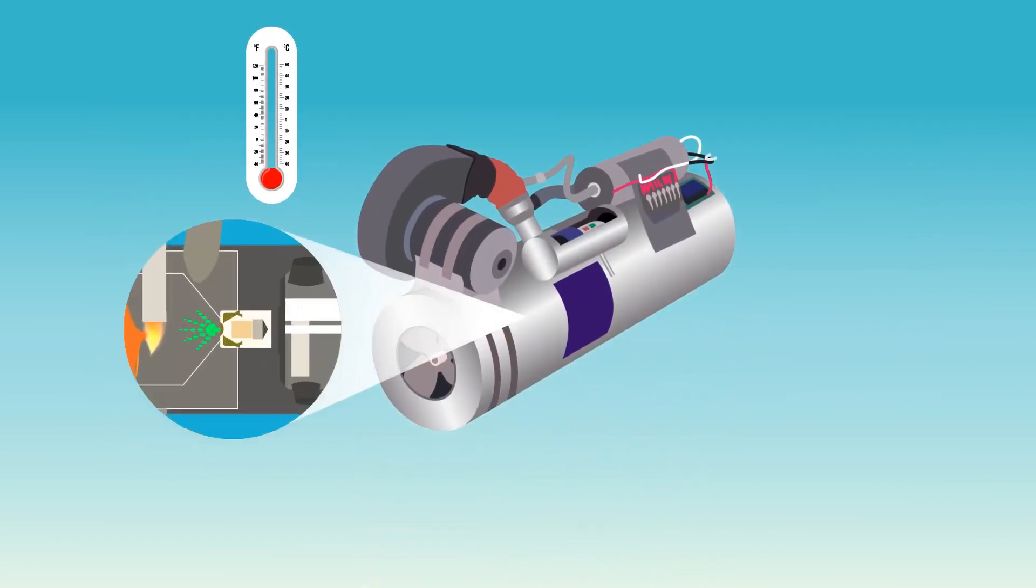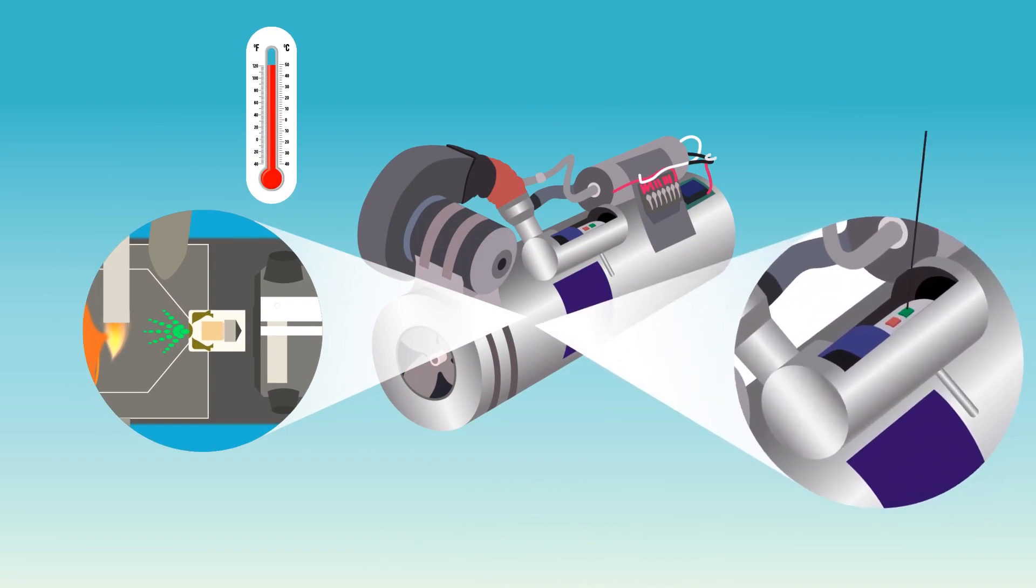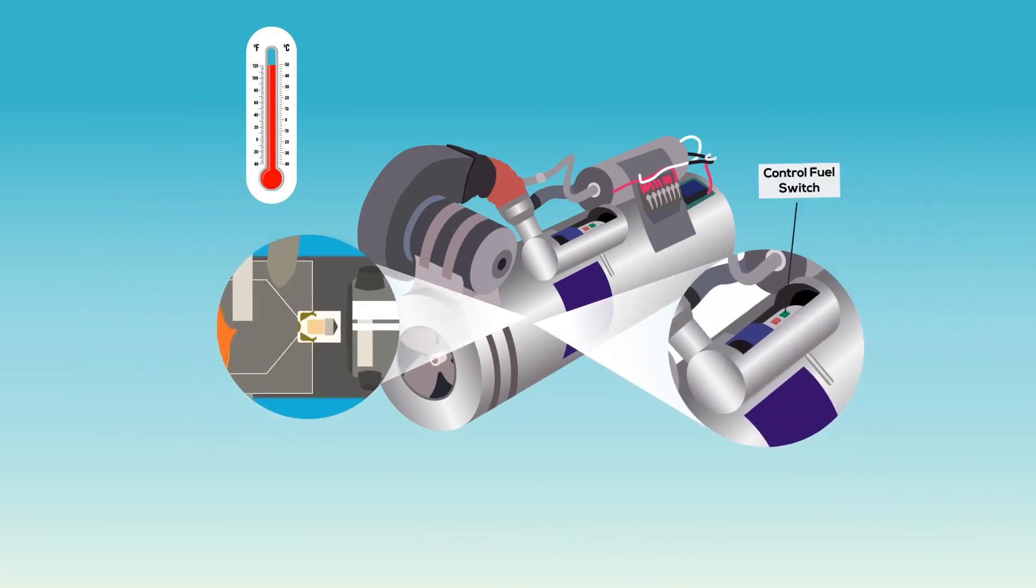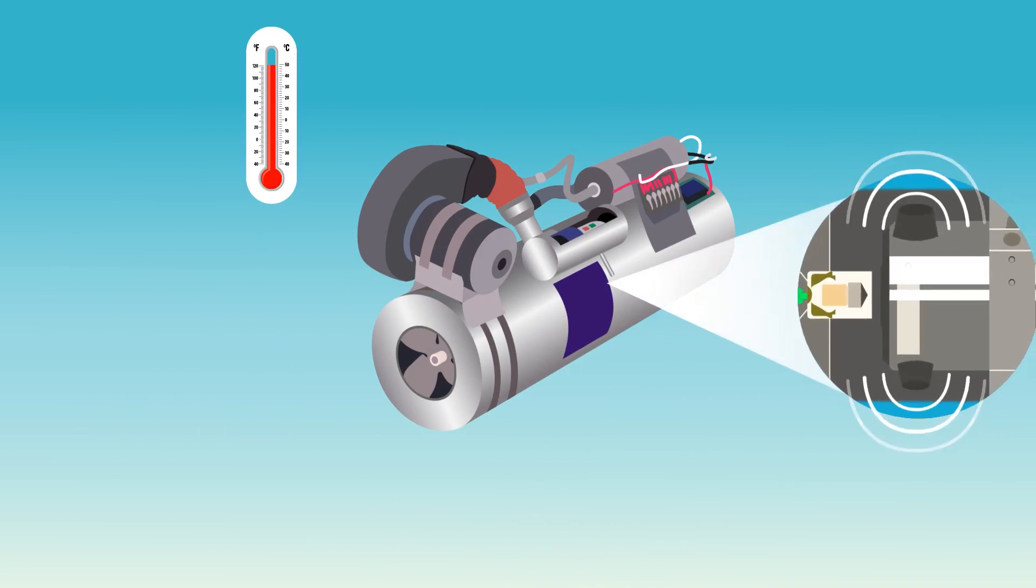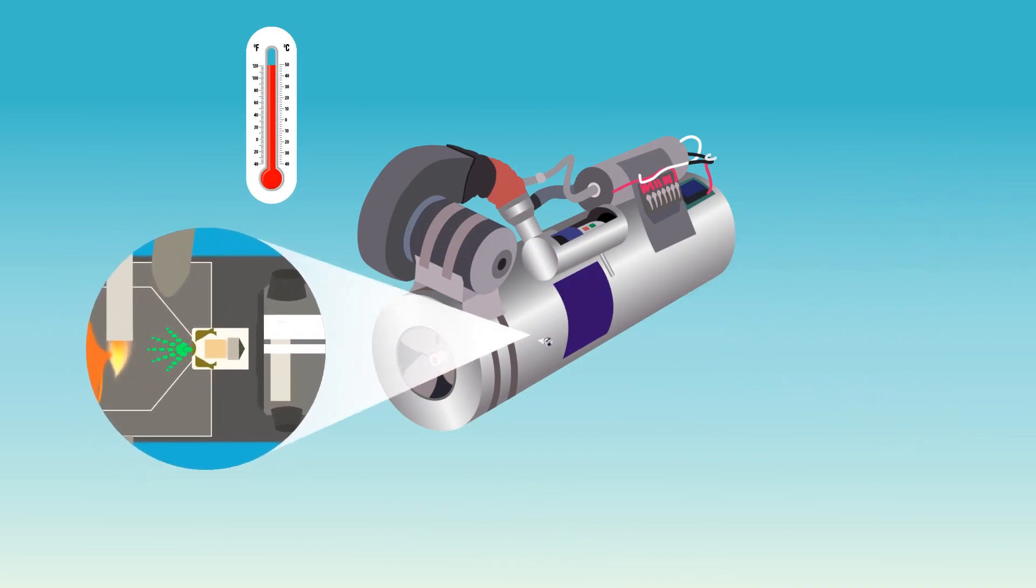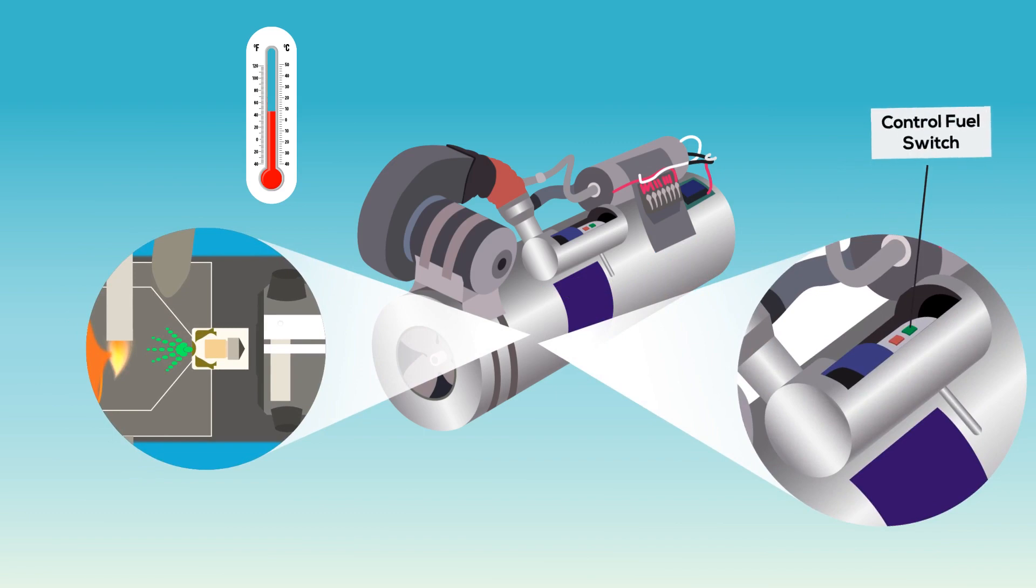As the thermostat reaches its preset temperature, it turns off the fuel solenoid and stops the flow of fuel into the combustion chamber. When ventilation air cools to the point that the thermostat senses that heat is required again, the thermostat turns the fuel solenoid on, and the burner starts again.